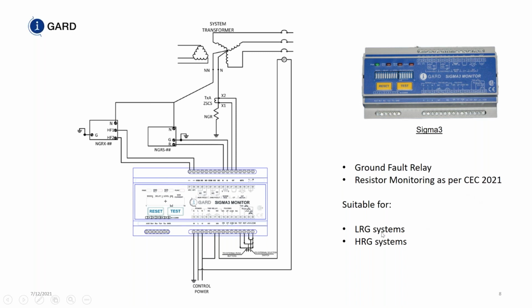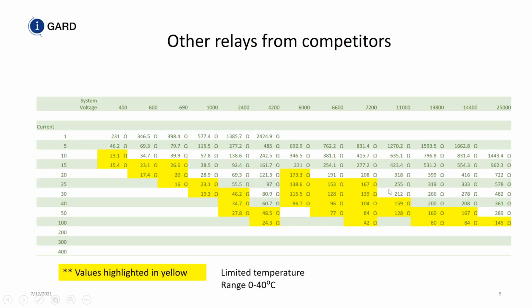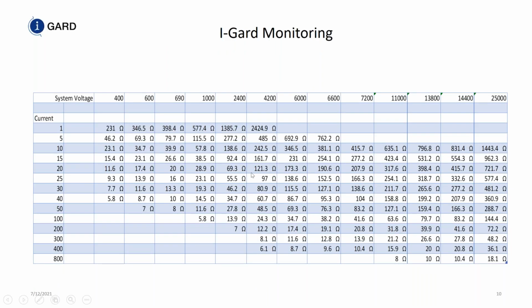So this works on low resistance grounding systems and high resistance grounding systems. More specifically for low resistance grounding systems, because if you have a 2400 volt, 400 amp, 10-second resistor, you basically have a 6 ohm resistor, and not many manufacturers can do that. As a matter of fact, some of our competitors published data that says their resistor monitors are only good for high resistance grounding systems. They're not intended for use on low resistance grounding systems. The I-Gard monitoring relay is good for high and low resistance grounding systems. In fact, this is the range from 400 volts all the way to 25 kV. These are the resistance values it's good for.